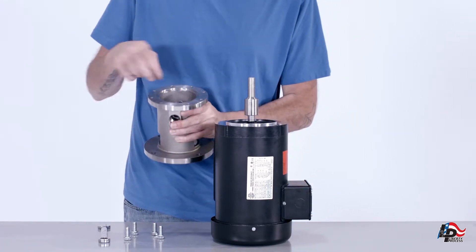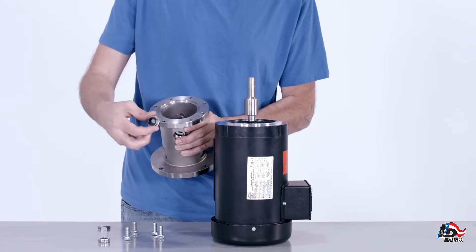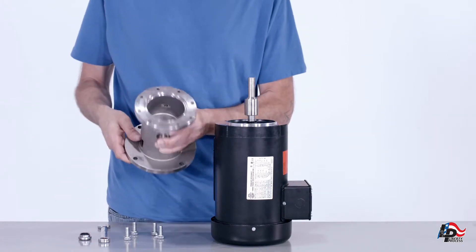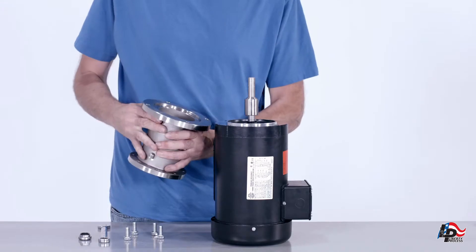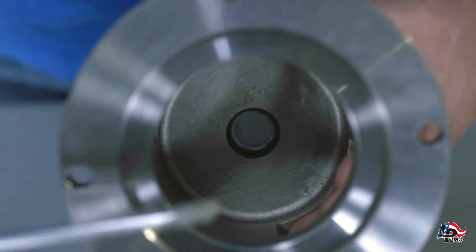Once the pump discharge casing is separated from the motor, you can remove the rotating face of the mechanical seal assembly. Turn the pump discharge casing over. Using your fingers, press out the stationary face of the mechanical seal.